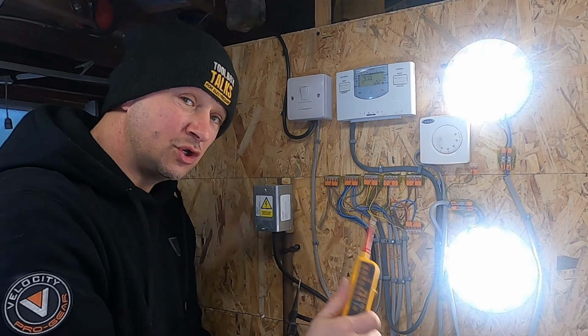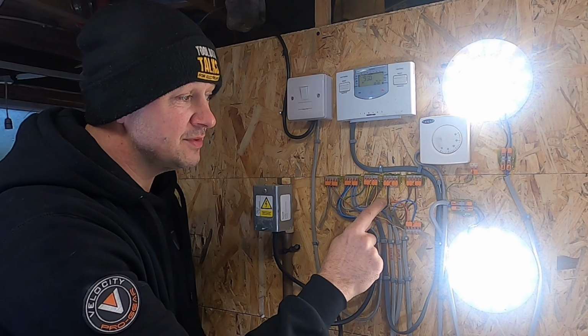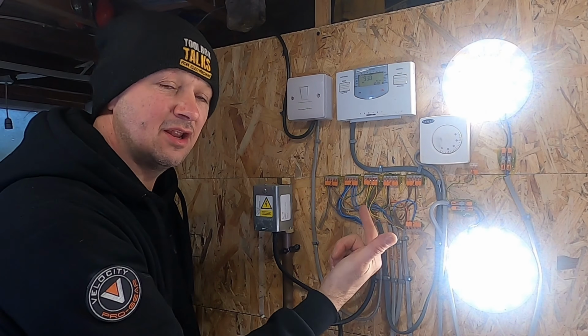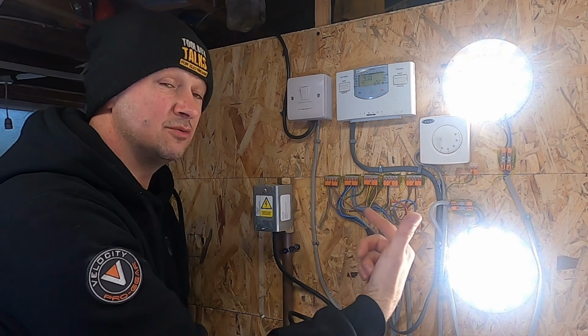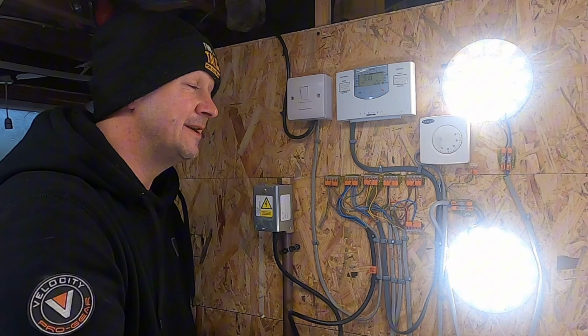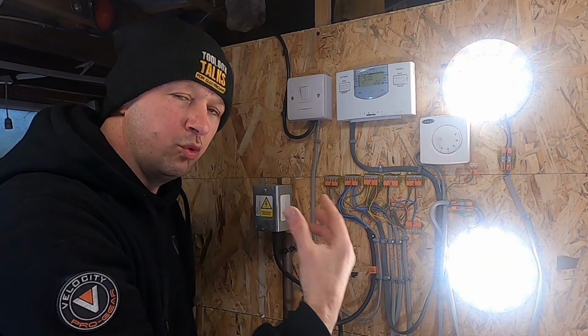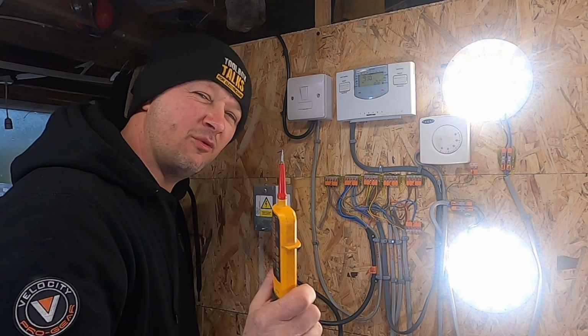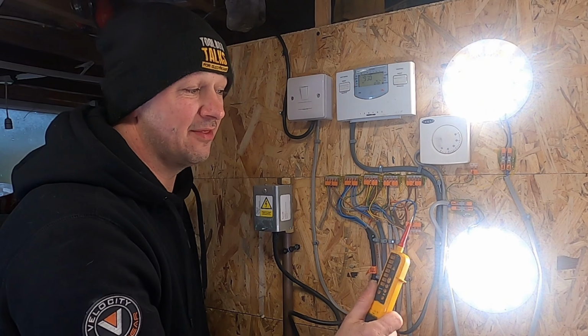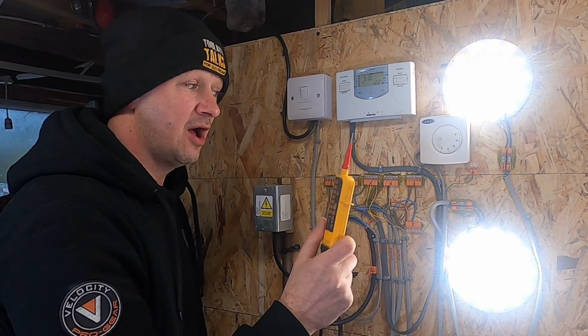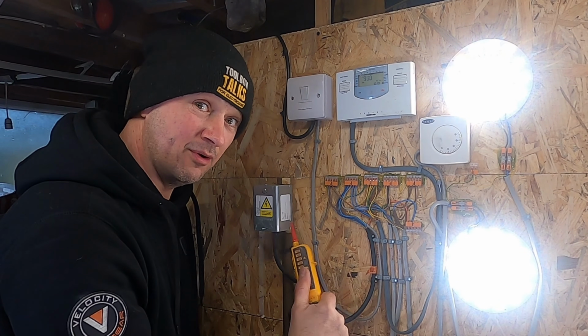So if you had 2-port valves and you were sending a signal to the pump, that pump would get alive and then send the live back to the signal, the 2-port valve of the central heating. Complicated, I know, possibly, but it wouldn't work properly. This is why I was wrong the first time and I had the pump live in with the signal live from the time clock and not the signal live from the 2-port valve.